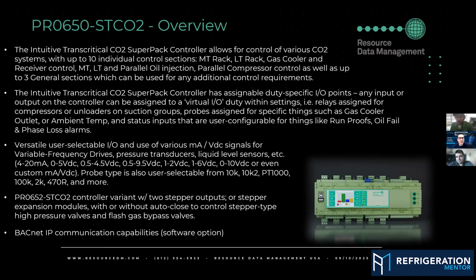Cody, what about you? You're doing a lot of the technical support now on the CO2? What are some of the calls that you've been getting? I get a lot of the proof lockout thing. To touch base on it, Chris is correct. So we'll see wiring incorrect, and then you'll also see the other thing is we're still running off mechanical. So our controller, all it's doing is sending a signal on off relay. You're still running through time delays, you're still running through low pressure switches, you're still running through all that wired up. Well, what'll happen is in our settings, we have time settings in there. Well, the OEMs will set them during testing period. They'll set them to 5 minutes, 2 minutes, whatever, and they'll leave them. Well, if the startup guys don't realize that those are set to that purpose and that our equipment's set for 1 minute return signal, it locks stuff out.